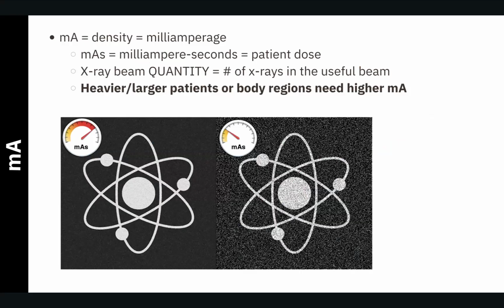maintain. So MA stands for milliamperage, and this is basically the density. And so the simplest way to think about this is the heavier the patient or the bigger the patient, the larger the patient, the more mass that there is, the more MA that you need in order to image that body part. And so this is really dictating the X-ray beam quantity. So looking at the number of X-rays in the useful beam.